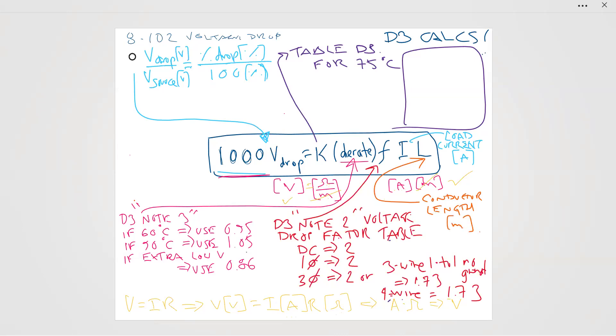How do you use this then to do the voltage drop calculations of 8-102? Well, you simply write down this formula. And you simply plug in what you know, and you solve for what you don't know. We can calculate voltage drop, we can calculate K from table D3, which I'm going to post in here. And we're going to have a nice little cheat sheet for this. We are going to derate K with the notes of D3 note 3, which are down here. And then we are going to multiply by F, which is the voltage drop factor table. And then we are going to multiply by load current and we multiply by conductor length and those are the relationships.